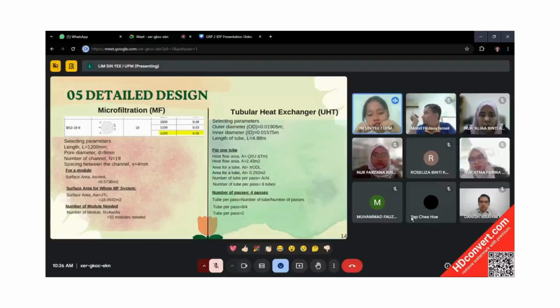For the tubular heat exchanger, we also select the parameters based on the TEMA. Outer diameter will be 19.05 millimeter, inner diameter 15.75 millimeter. Length of the tube will be 4.88 meter. Then to calculate the heat flow area, which means the surface area required for the heat to pass through the tube, we use Q over U, Q divided by U multiplied with the temperature difference, and we get 2.43 meter square.